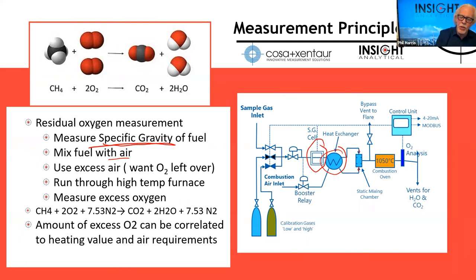So if we knew exactly the fuel composition, if we knew it was methane, we know that we need to put in precisely twice as many oxygen molecules as we have methane molecules, and we could get a perfect burn of the methane. But the oxygen molecules don't come on their own. They're going to come in, of course, with some nitrogen. So we have to add in the fact that there's some air in there. And then as the fuel changes, we think of natural gas as being methane, but it's not. It's methane with a bit of ethane, a bit of propane, a bit of butane. And those other components, as they change around, are going to change what the optimum amount of air to add to the burner is. And that's where we use this measurement to say, based on the fuel changes, what's the optimum amount of air I should be running to the burner?